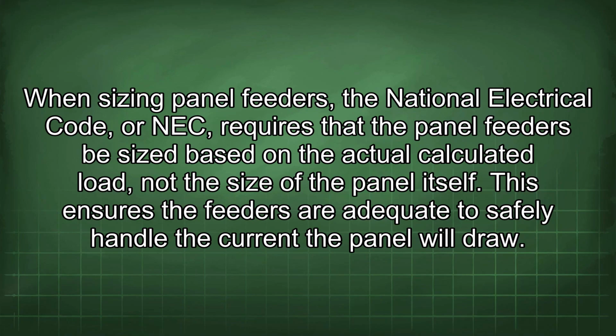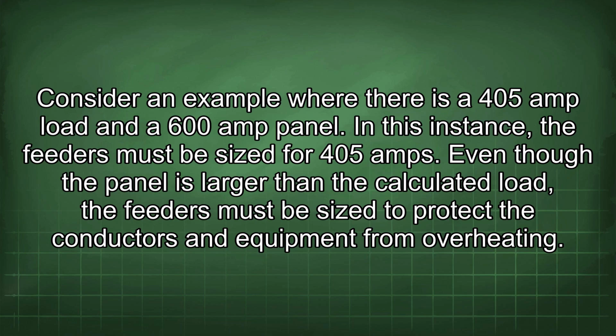When sizing panel feeders, the National Electrical Code, or NEC, requires that the panel feeders be sized based on the actual calculated load, not the size of the panel itself. This ensures the feeders are adequate to safely handle the current the panel will draw. Consider an example where there is a 405 amp load and a 600 amp panel. In this instance, the feeders must be sized for 405 amps.